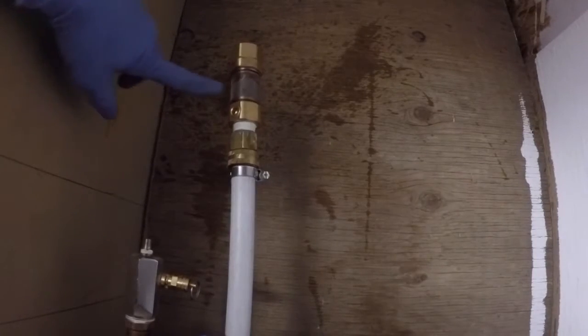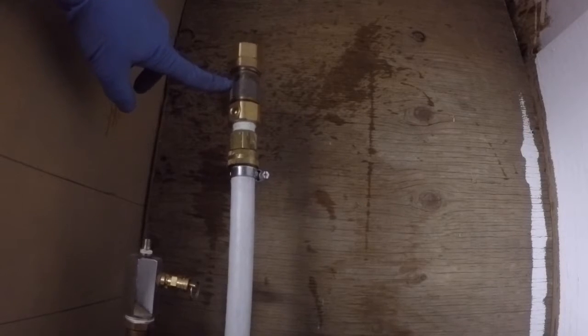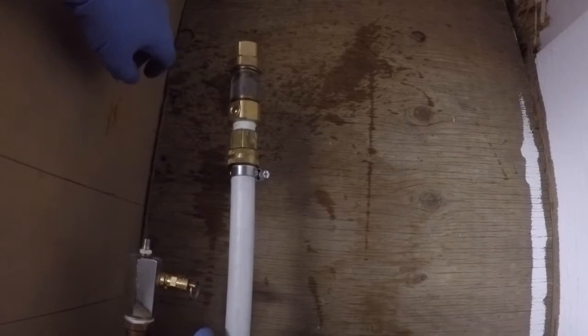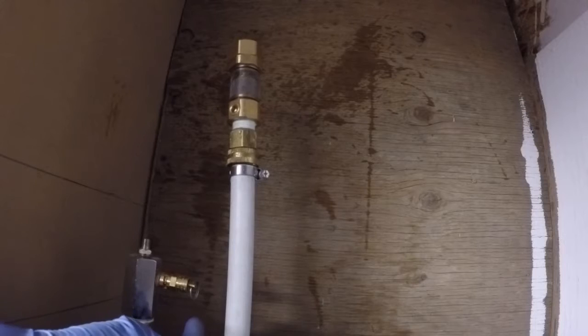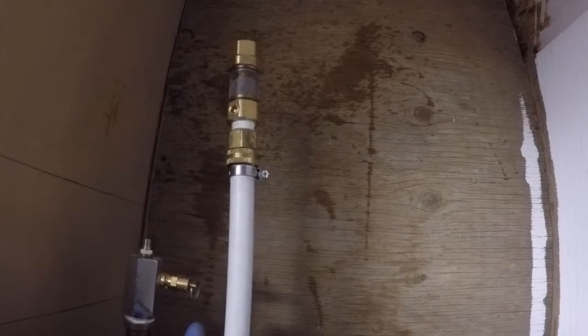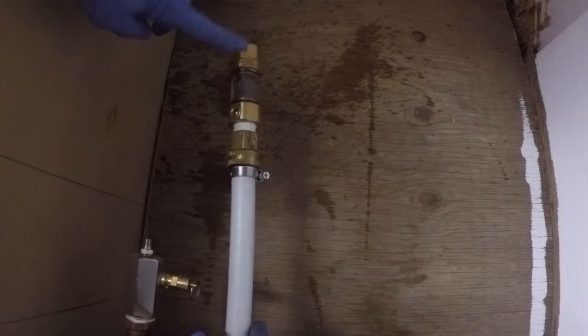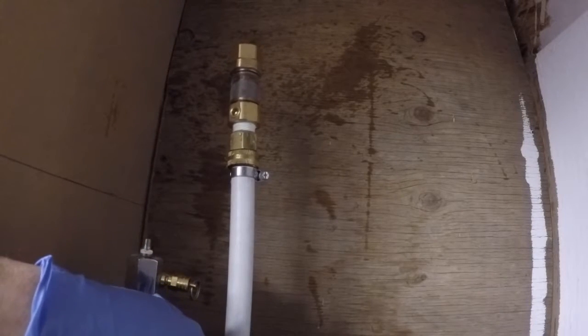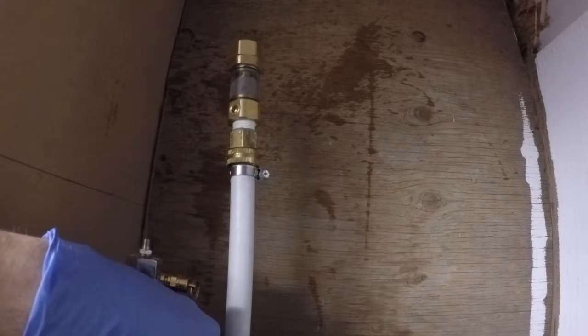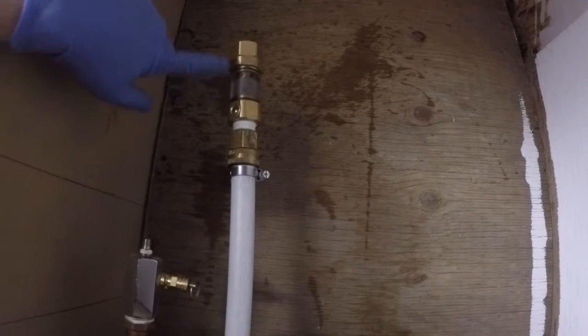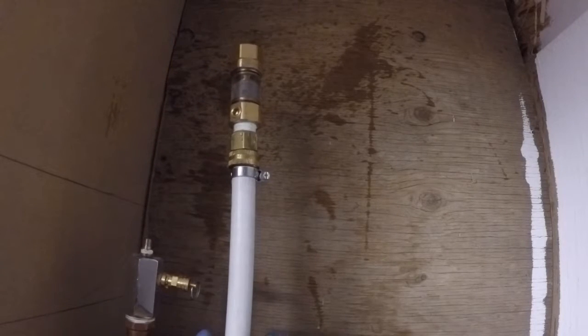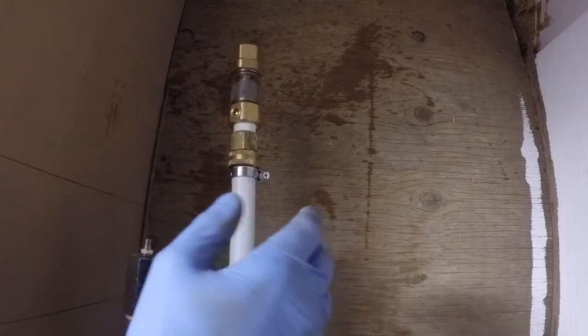I'm not sure if you could see actually, but I could. If you look closely at the top of this filter, you can see there's water sitting in there. And if I open the valve, you'll see that water level rises. If there's any air in the system, it will come out through the top of the fill filter. And we can see the level of water rose. No air came out, no bubbles came out, so there's no air in the system.